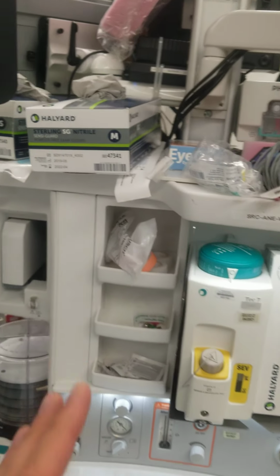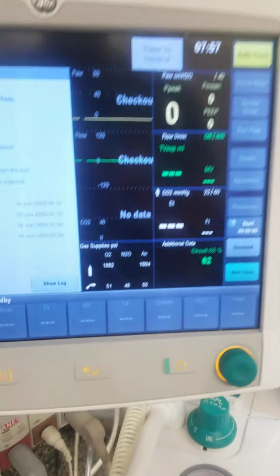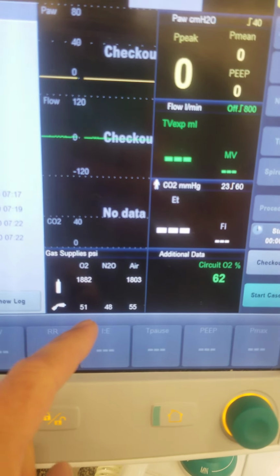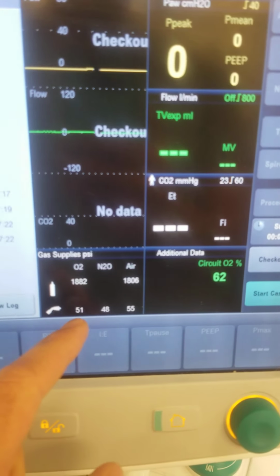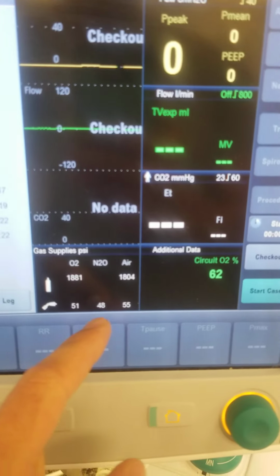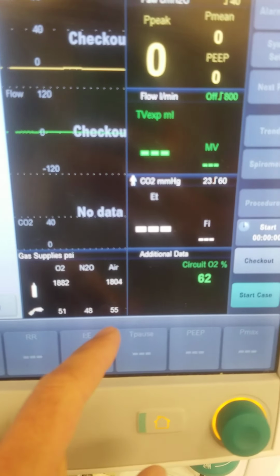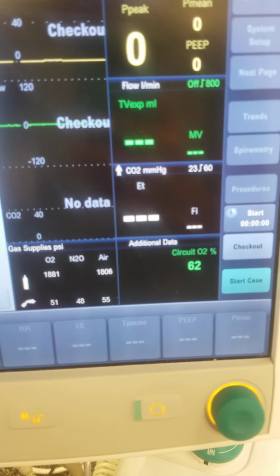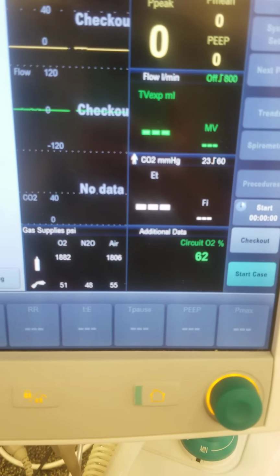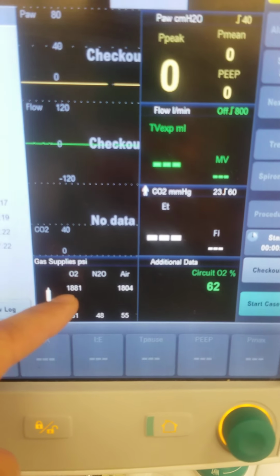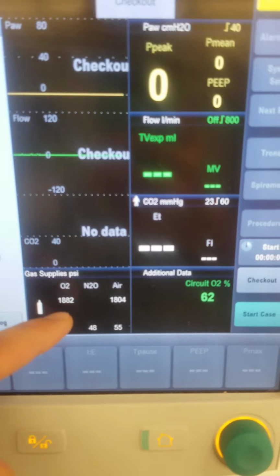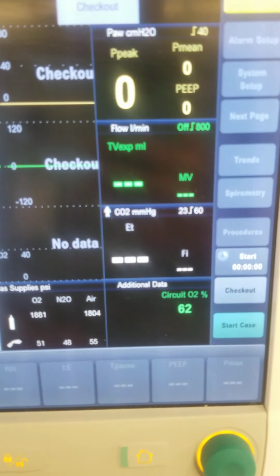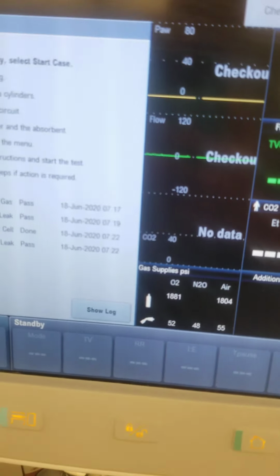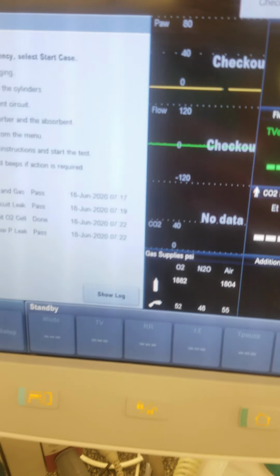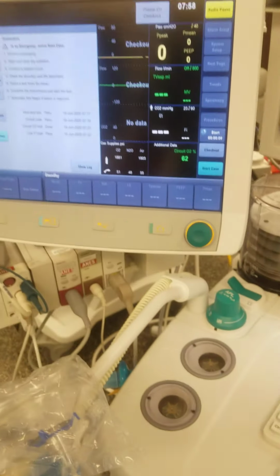Since I'm already looking at the main feeds, I'm going to check the main feeds. Everything should read within about 3 points of 50. So I got 50 under oxygen, 50 under nitrous, and 50 under air. If it's ever less, you should call someone. There's a problem. And now I check what my emergency bottles are. So I've got 1800 for O2 emergency and air is 1800. If it's less than 1000, you should replace it. It's kind of the rule of thumb, so you've always got a good reserve.